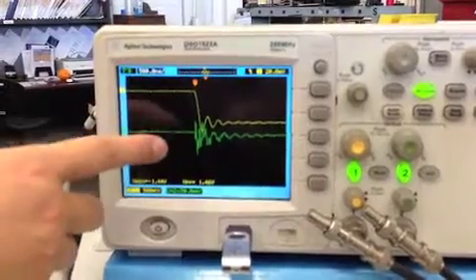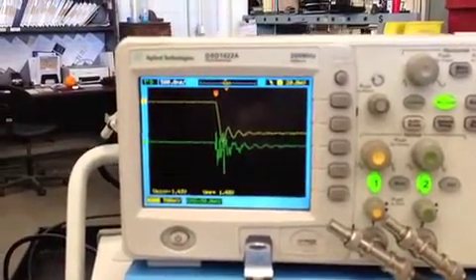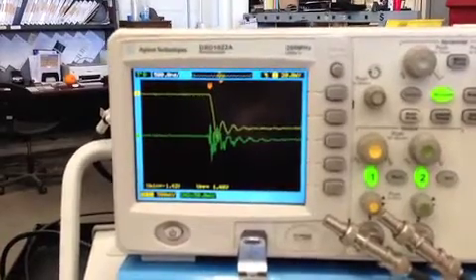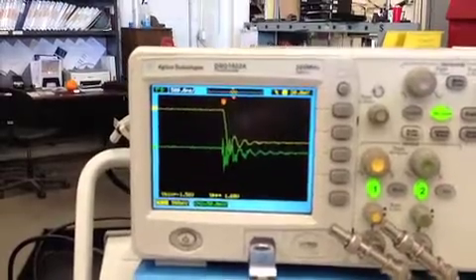We have to watch very carefully at the graph. She's going to raise the voltage and you'll start to see some activity there. That's indicating partial discharge is occurring.